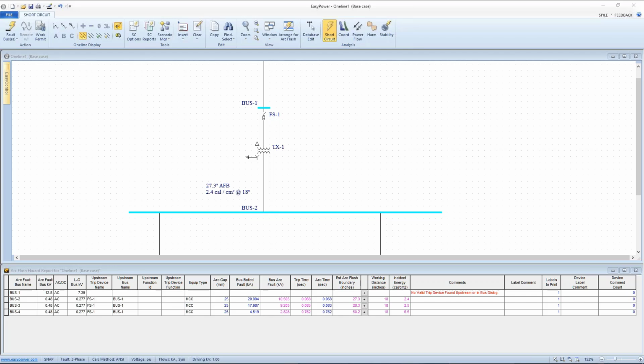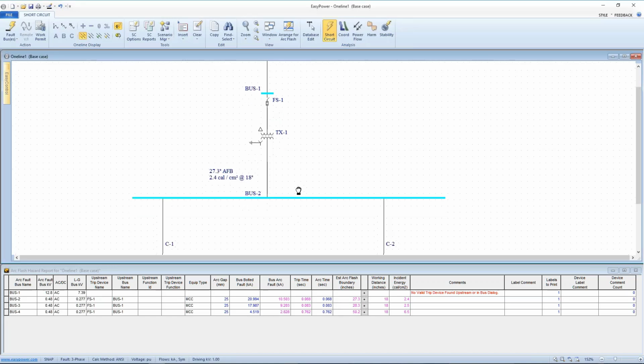Based upon the type of bus that we have defined, the arc flash gap, the space between any bare conductors, is 25 millimeters. We already knew there was 20,994 amps of bolted fault current available at that bus. According to the IEEE model, the maximum current an arc would draw under these conditions would be 10,500 amps. According to the manufacturer's datasheet for this fuse, at 10,503 amps, that fuse will blow or clear in 68 milliseconds. So that gives us the ability to calculate the arc flash boundary and incident energy.